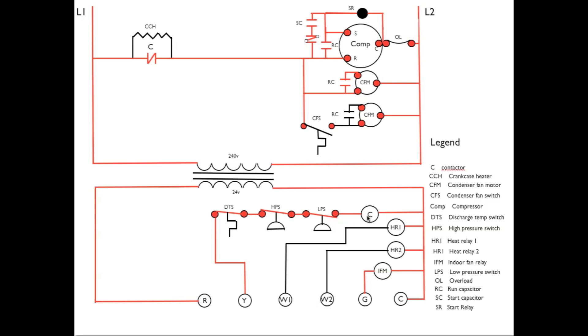Okay, to energize C. C is energized, C contacts close. Power passes through, I'm going to do the condenser fan motor first, down through to the run and start winding on condenser fan motor, and energizes the fan motor.